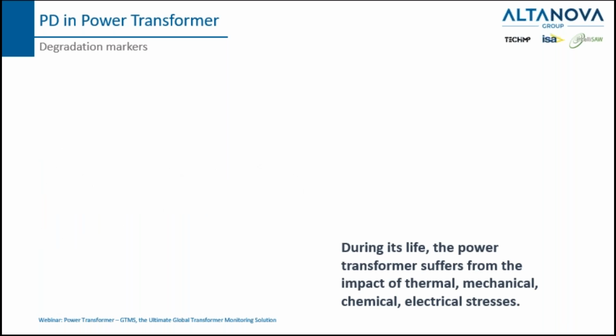We have seen that during its life, the power transformer can suffer from a lot of stresses. I mean thermal, mechanical, chemical, and for sure electrical stresses. And these stresses cause a degradation of the general condition of the transformer, in terms of reduction of the electric strength, or the mechanical strength, or the thermal integrity of the windings, for example.